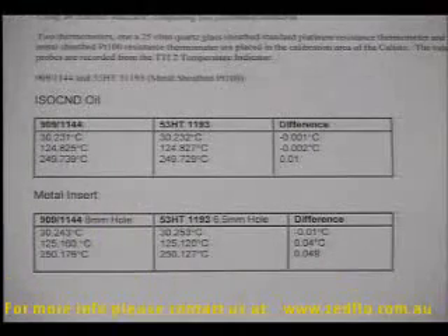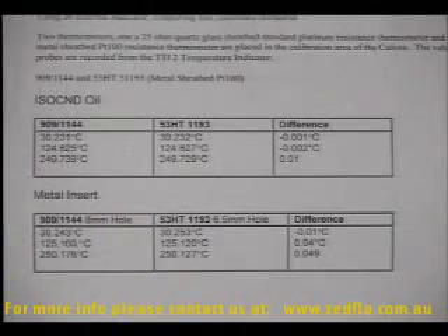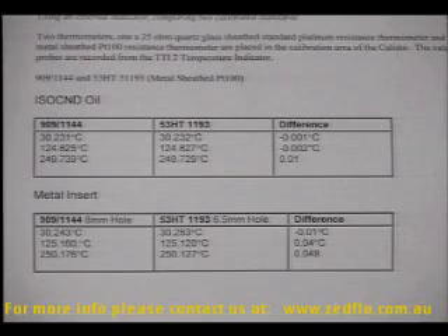This last sheet shows how you would normally use a metal block insert. We've got a standard quartz 25.5 ohm thermometer in one of the holes, and we have a typical metal sheath 6 mm diameter sensor in another of the holes. We can make a measurement since both are calibrated at 3 different temperatures. We look at the difference, and the actual difference we get is at worst case 10 millikelvins, that's in oil. If we use the metal inserts, here we get a worst case error of about 0.05 degrees Celsius, 50 millikelvins at 250 degrees Celsius, which is probably the smallest uncertainties ever achieved for a metal insert.